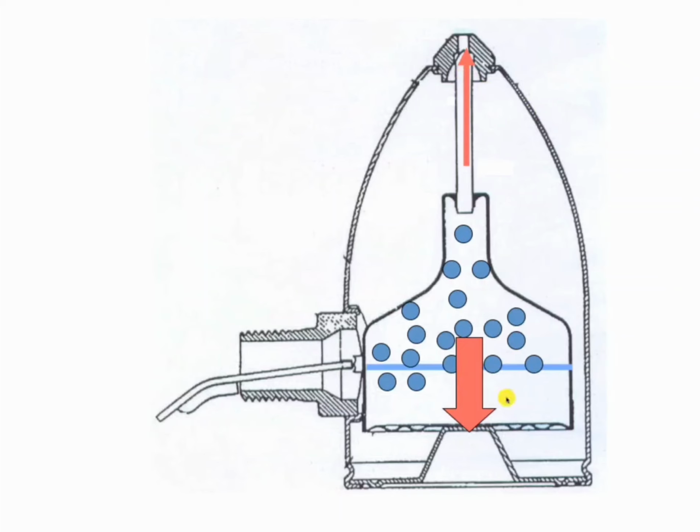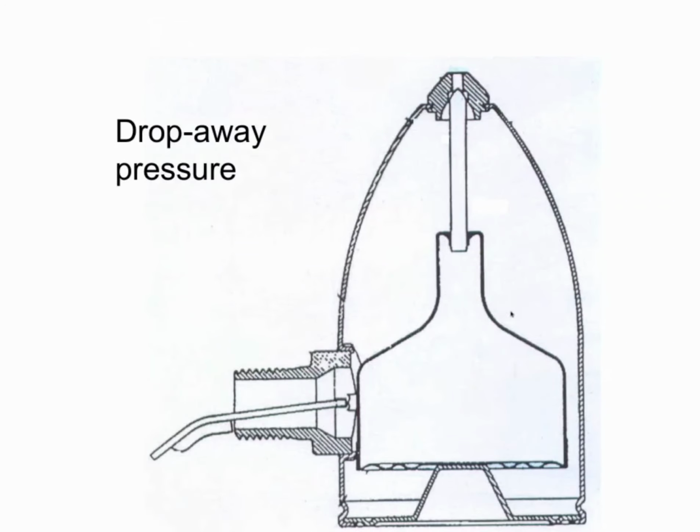And this is kind of like hanging in space because it's sitting up there. And even when it cools down, it's still hanging in space because the steam pressure is pushing against the bottom of it, keeping it closed. So what we want to happen is the float to fall so that we can have venting again. And that's where this thing called drop-away pressure comes in. Vent valve manufacturers in their literature, they call it either...